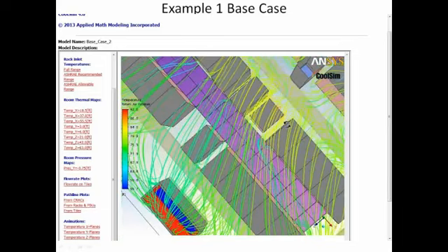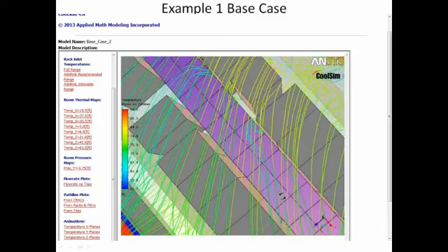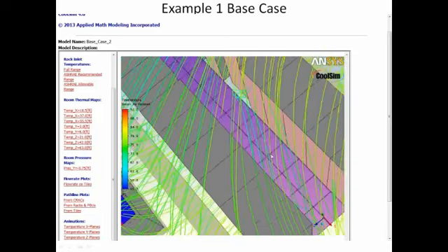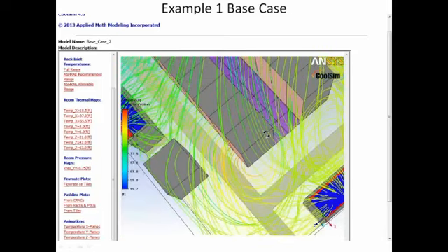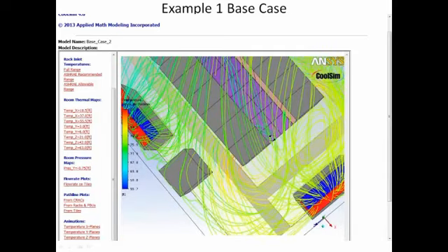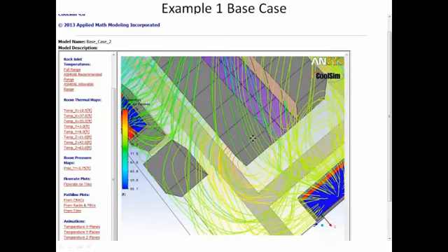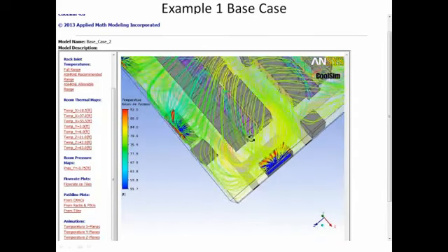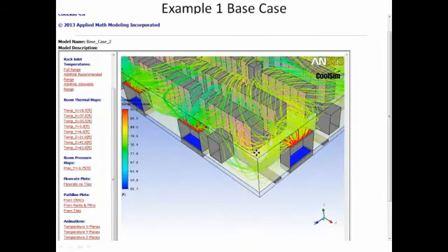One of them is right here. This is rack recirculation, where it's coming out of the rack, coming back around through this CRAC between the two servers and getting sucked into the intake. Now, the reason it's doing that is it's trying to find its way back to that CRAC unit. But on its way, it gets breathed into the intake. Same case here on this end. We've got wraparound right here, where it's going around the end and wrapping and being drawn into the intake. So that's your fundamental problem with this overall design. It's not a surprise to you and I.